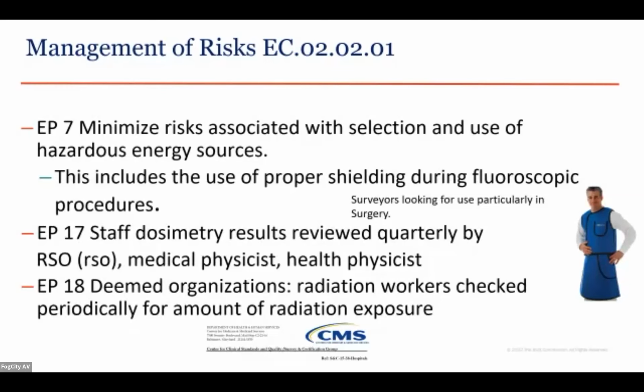Staff dosimetry reports. So EP 18 is really based on a CMS requirement that says that anyone classified as a radiation worker in the healthcare environment, hospitals, needs to be checked periodically for radiation exposure. So that's the one that says you need to have a badge or other equivalent monitoring to determine what your radiation exposure might be.